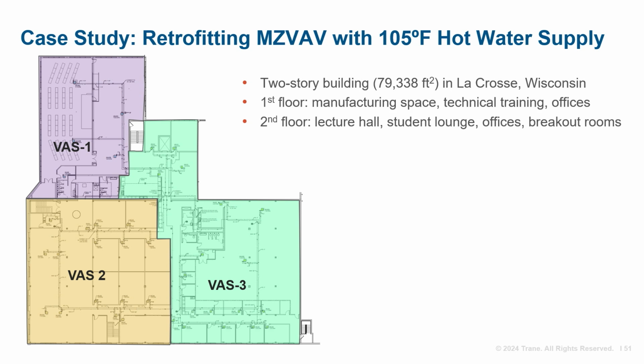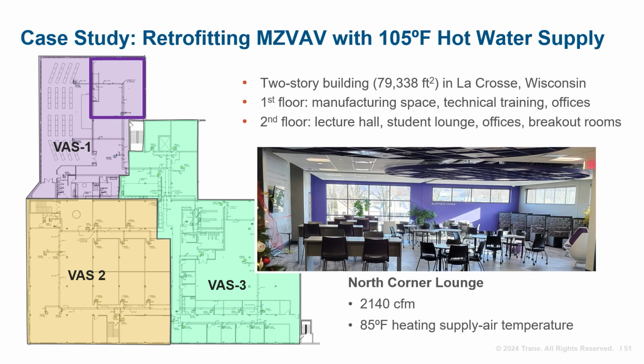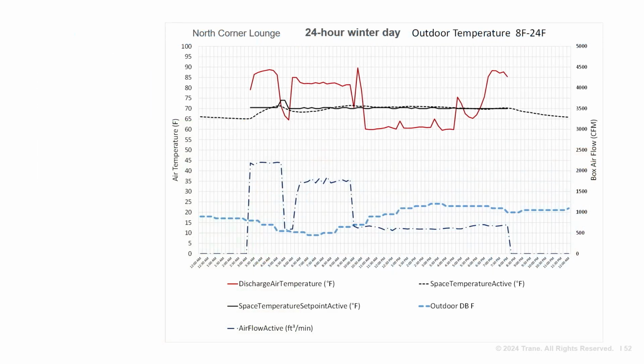To demonstrate the VAV box control performance, let's look specifically at this corner zone on the student lounge. It's 832 square feet and conditioned with a VAV box with 2140 CFM design airflow and a 4-row coil selected for an 85 degree heating supply air temperature. This chart demonstrates how the box successfully conditioned the zone on an 8 degree winter day.